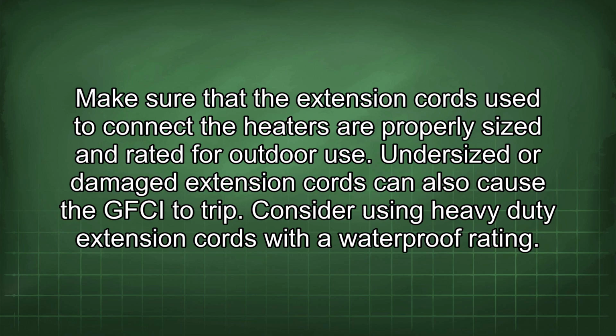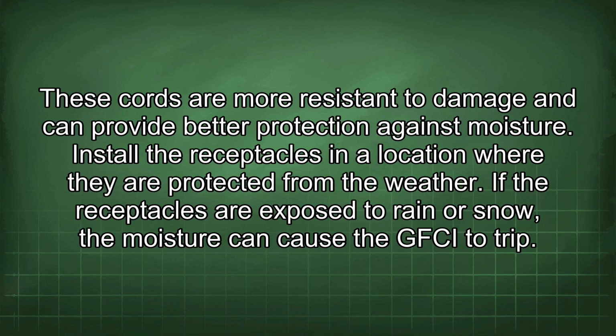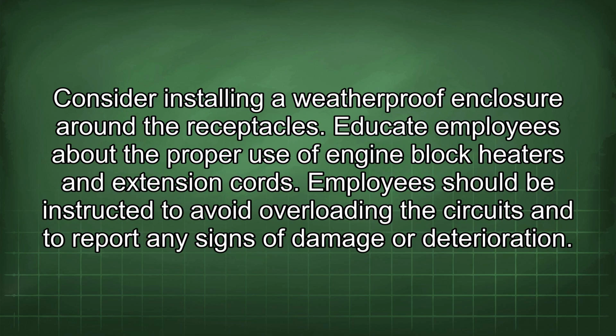Consider using heavy-duty extension cords with a waterproof rating. These cords are more resistant to damage and can provide better protection against moisture. Install the receptacles in a location where they are protected from the weather. If the receptacles are exposed to rain or snow, the moisture can cause the GFCI to trip. Consider installing a weatherproof enclosure around the receptacles. Educate employees about the proper use of engine block heaters and extension cords. Employees should be instructed to avoid overloading the circuits and to report any signs of damage or deterioration.